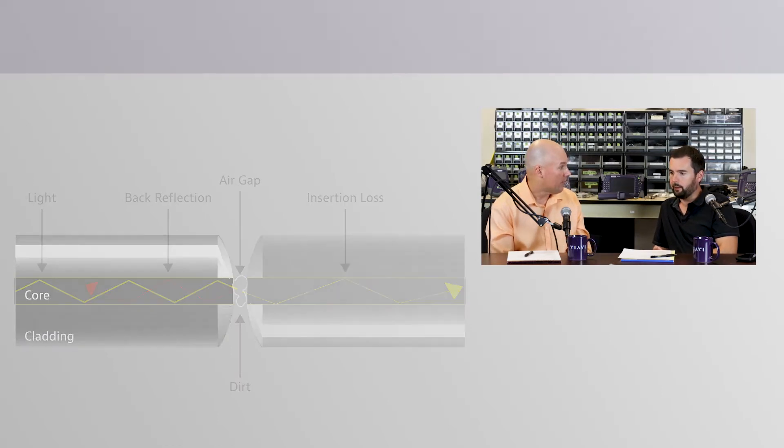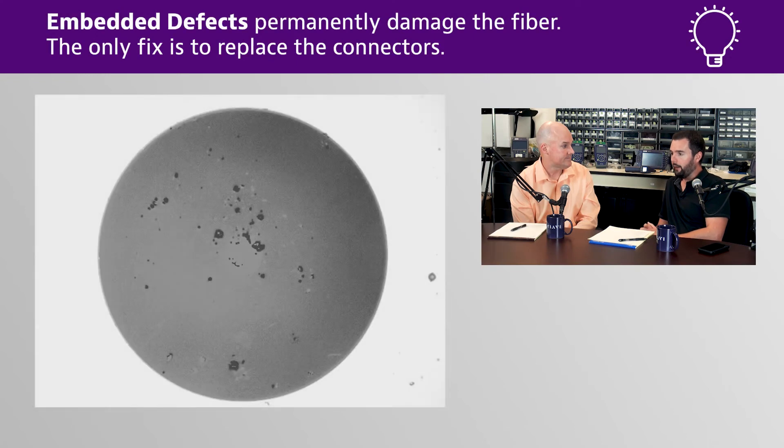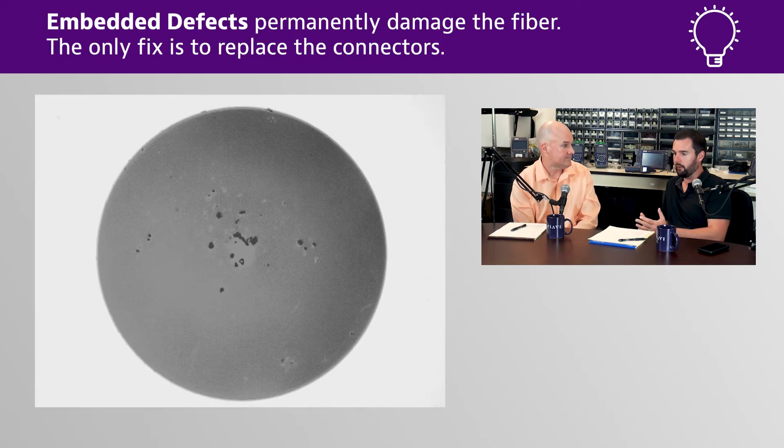Tyler, what do you see from an inspection standpoint with dust — what happens to the end face if you start mating and then try to clean retroactively? Well, you find it doesn't come off. Somebody runs the trace, sees a problem, goes to clean it, and it just doesn't come off — it's embedded in there. Now they've got a bigger problem; they're going to have to change that connector, get out the fusion splicer, and shut everything down for a day or so.